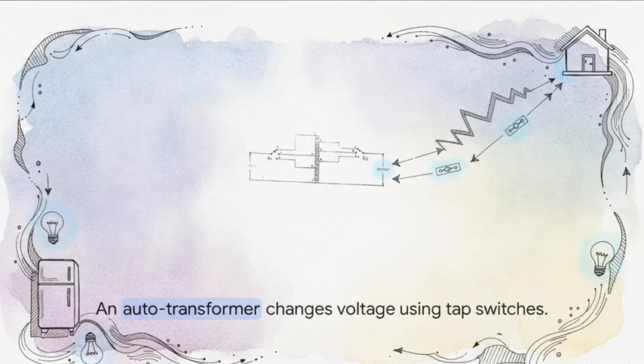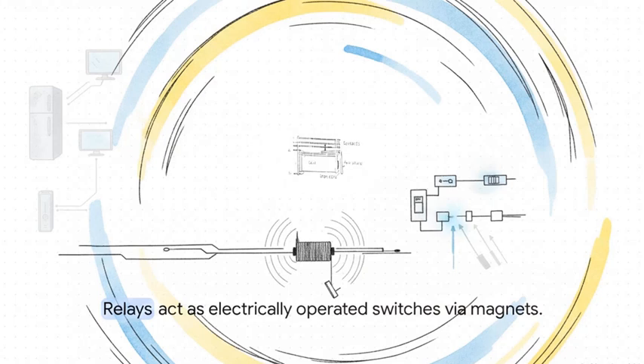Now, this basic concept builds into what's called an autotransformer, which is what you'll actually find inside these devices. Instead of two completely separate coils, the main transformer here has just a single, continuous winding that does double duty as both the primary and the secondary. The truly brilliant part here is the tap changing mechanism. We've got automated switches that change the taps along this single continuous coil to instantly select a completely different turns ratio, automatically adjusting the voltage up or down based on whatever the house's power grid is doing at that very second. And the actual muscles making those crucial tap changes, those are the relays.